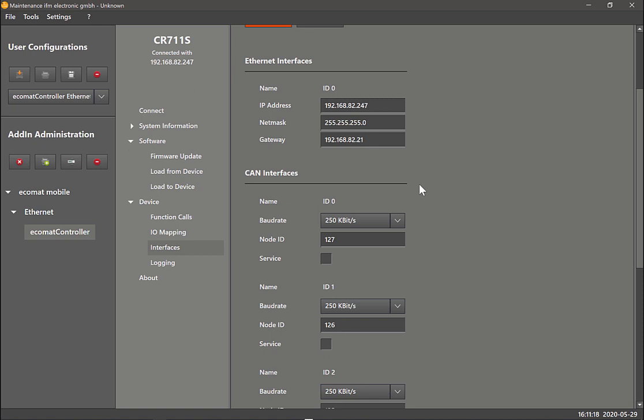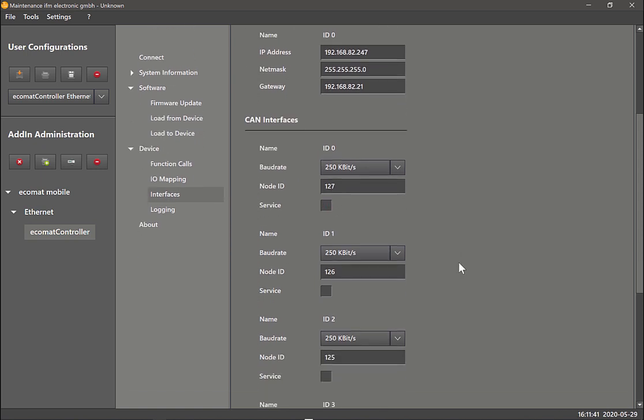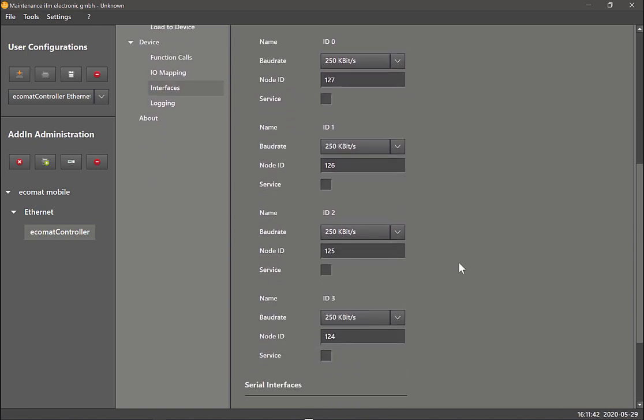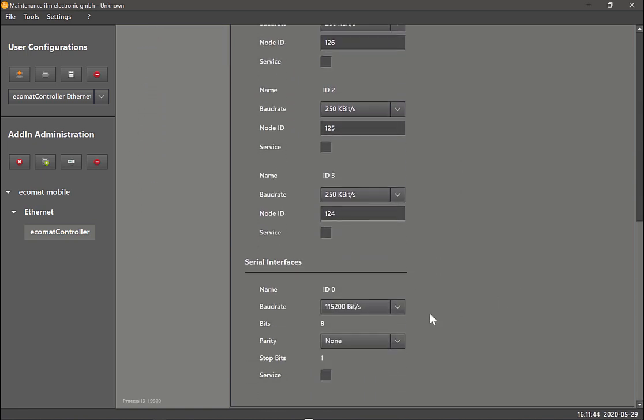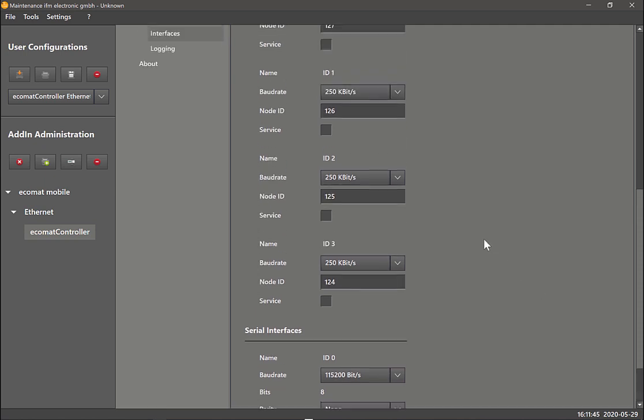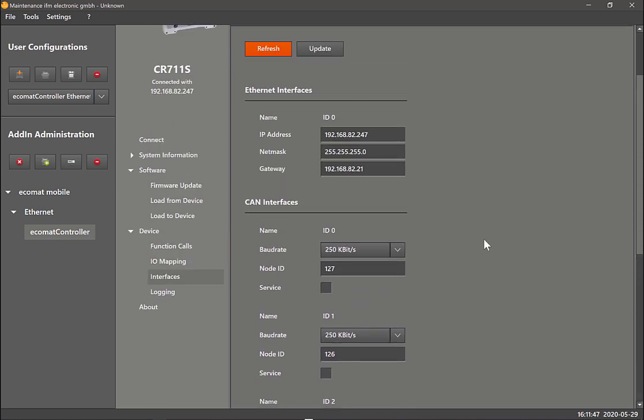Before I do that, just a quick note. You see this service option here? It's unticked at the moment. The reason we have the service option is if you are planning to use any of the CAN interfaces to download the program in the controller, you need to have that ticked. But if you're only going to use the ethernet interface, I would highly recommend to untick all of the service options, even on the serial port.